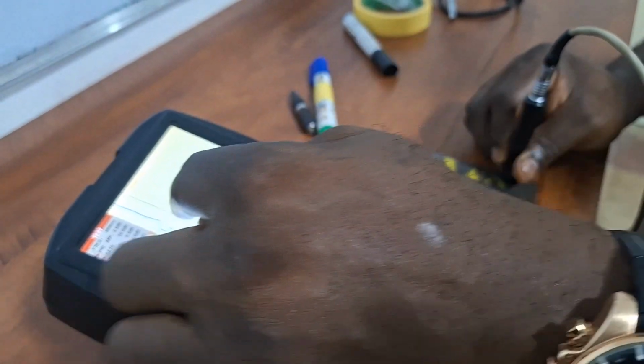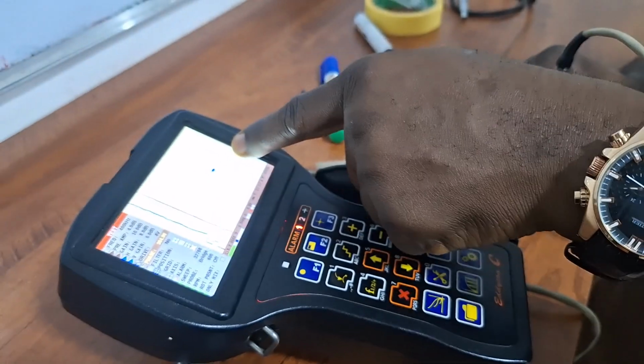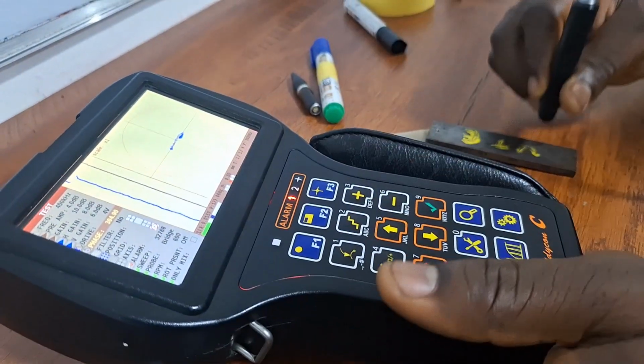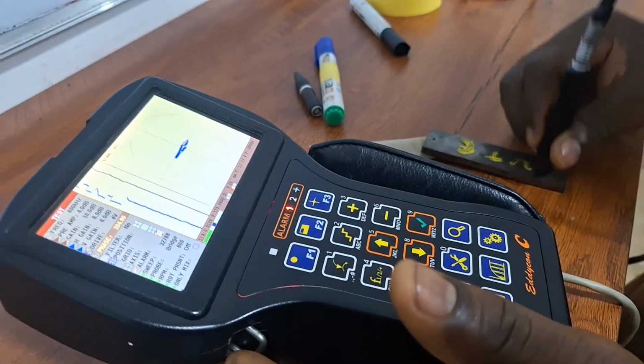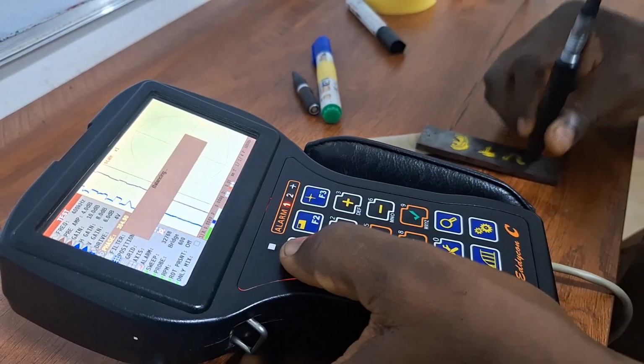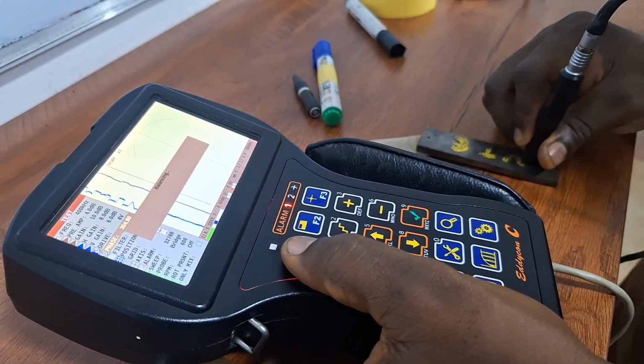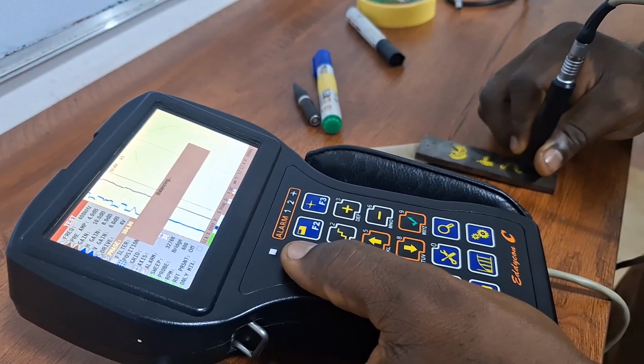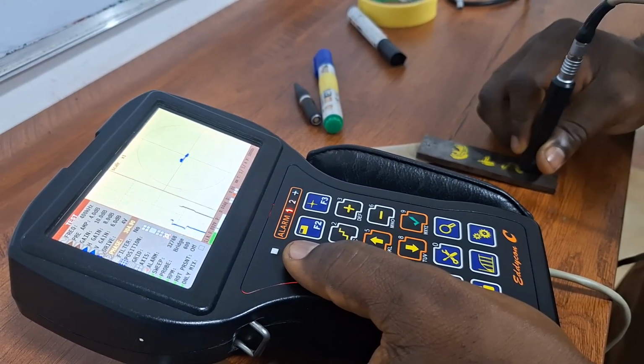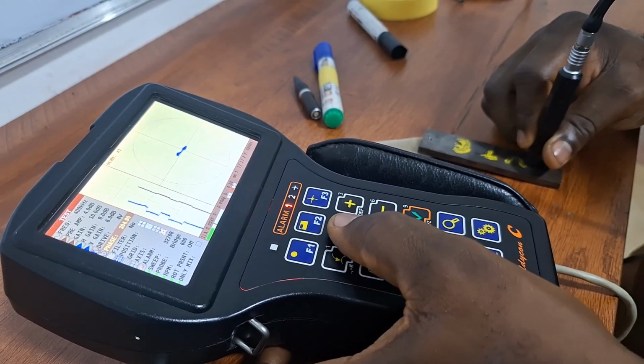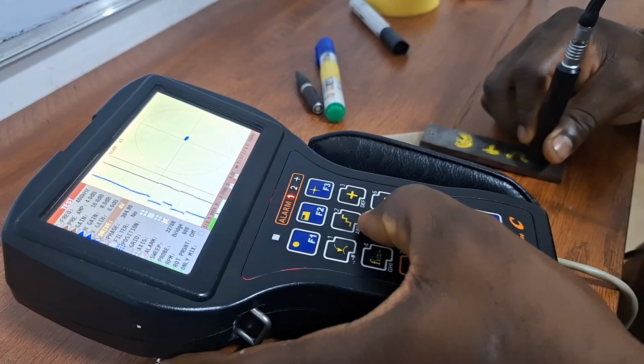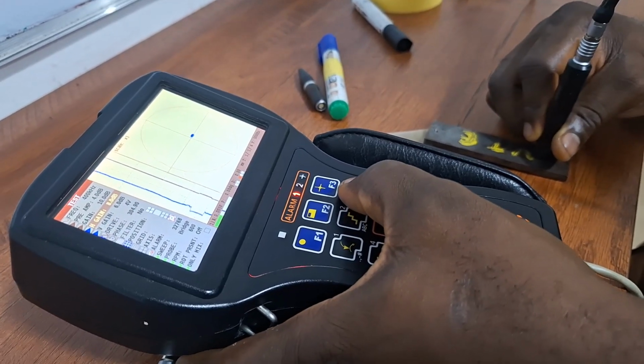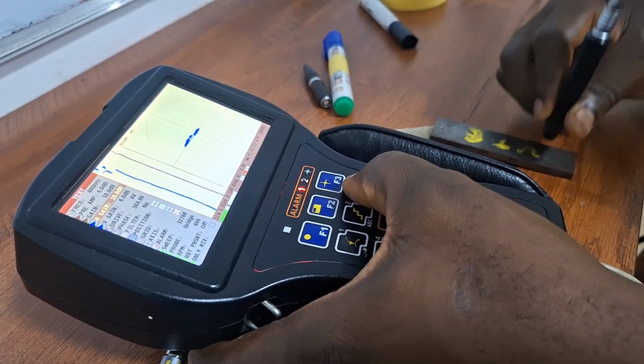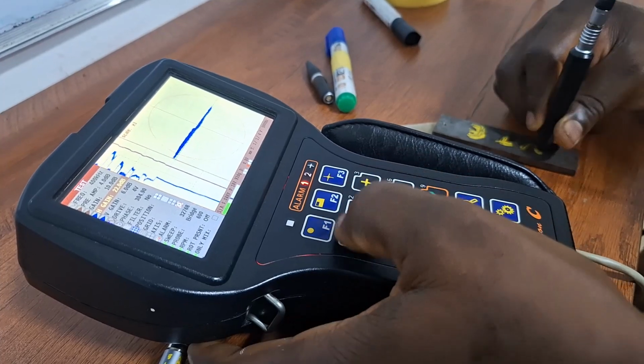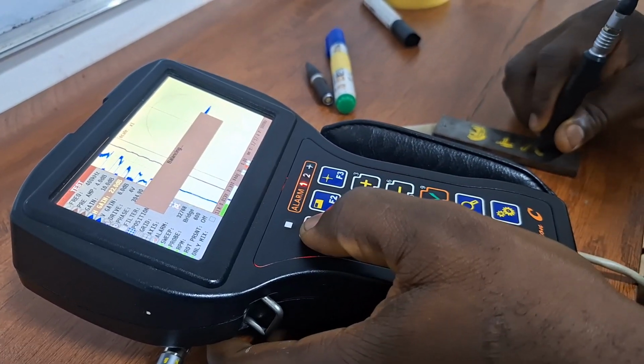Why do we need to do that? Because if you start taking your angle, this is 0 degrees, this is 90, this is 180, 270, 360. So it's usually better for horizontal left. We balance again and see how it comes out. If it is horizontal, it's horizontal. But if we now look at the gain, we go to the vertical gain and increase the vertical gain and see what happens. We balance.